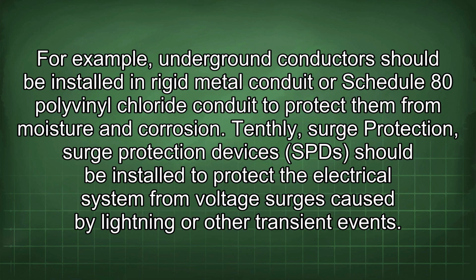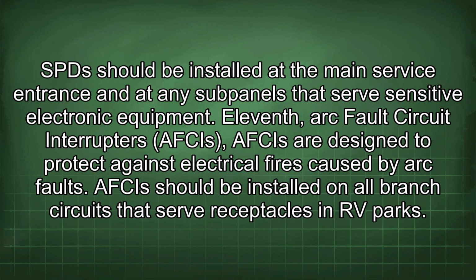Tenthly, surge protection. Surge protection devices (SPD) should be installed to protect the electrical system from voltage surges caused by lightning or other transient events. SPDs should be installed at the main service entrance and at any subpanels that serve sensitive electronic equipment. 11th, arc fault circuit interrupters (AFCIs). AFCIs are designed to protect against electrical fires caused by arc faults. AFCIs should be installed on all branch circuits that serve receptacles in RV parks.